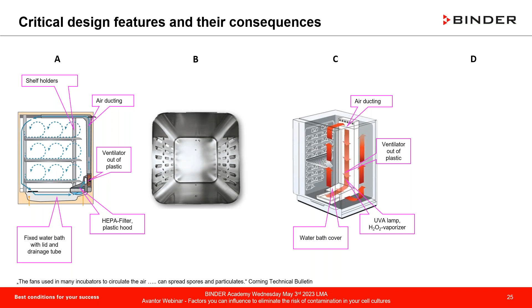This model C is not working with a HEPA filter, a particle collector. They're actually working with UVA behind the air duct system, and hydrogen peroxide at 6%. When operating that—we'll touch on that later—you definitely need safety glasses and safety gloves due to the aggressive chemical. That's what is stated in the user manual for version C. Then you have a water bath cover, additional contamination-prone surface, but the water pan can be taken out and autoclaved.